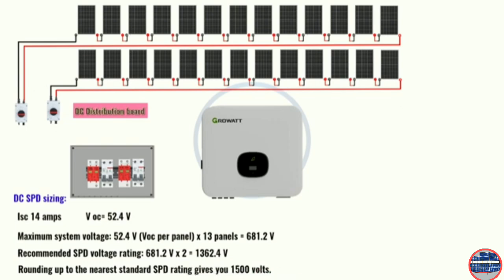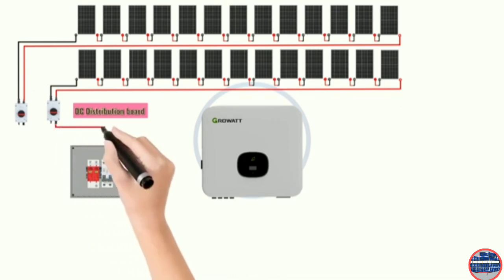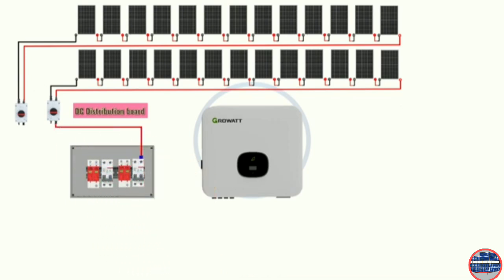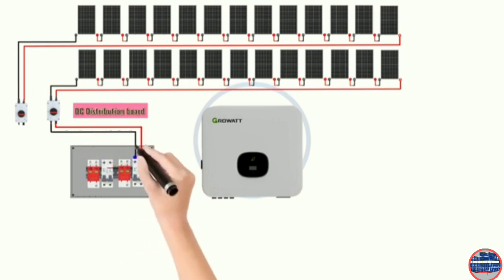Additional factors to consider. Number of strings: if you have multiple strings, each string should have its own SPD. Isolator switch to MCB connection. Connect the positive output of the isolator switch to the positive input of the DC MCB. Connect the negative output of the isolator switch to the negative input of the DC MCB.